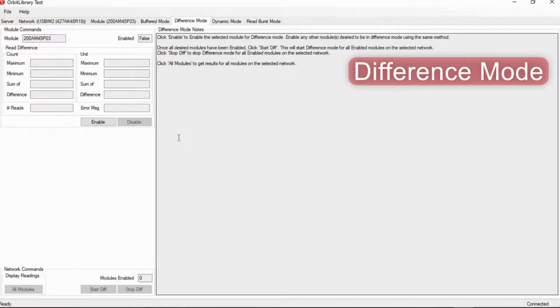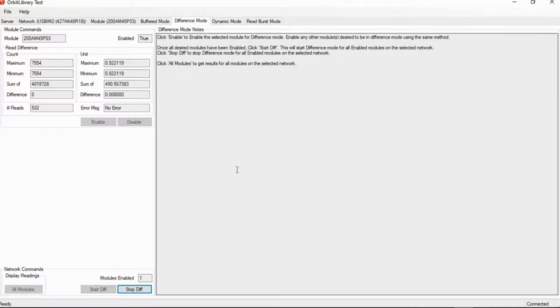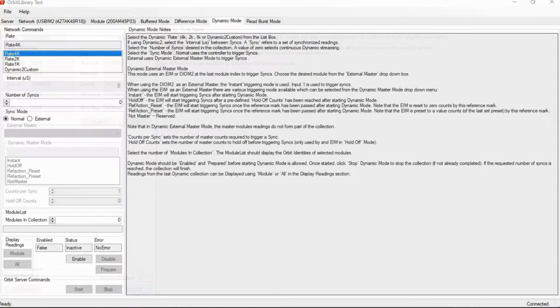Then we have difference mode. Again, the Orbit module can track the maximum, minimum, and difference and also be extracted on command. So we'll just demonstrate it here. I'm just going to click Enable, and then I will click Start Difference Mode. So now you'll see the maximum and the minimum, as I move the probe up and down, you have a minimum reading, maximum, then the difference calculated right there.